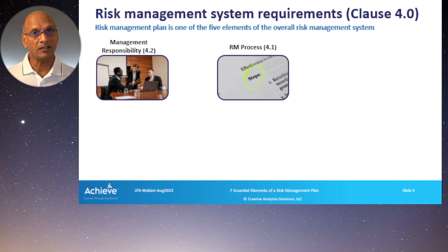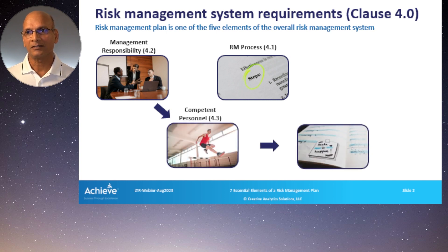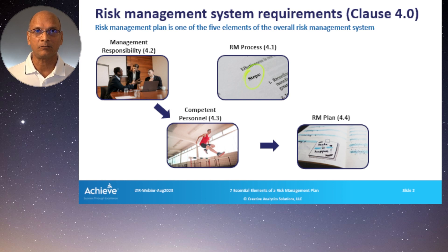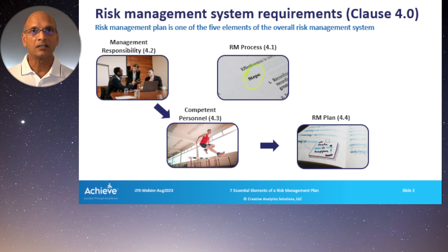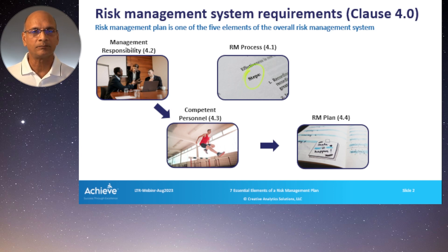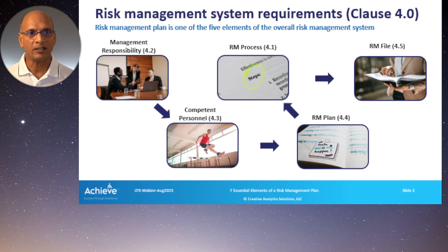Before the process can start, we need management responsibility to be clearly defined — that's in clause 4.2. They will assign competent personnel who would set up the risk management plan. All those pieces have to be in place first. The risk management plan is very focused and targeted for the particular product you are working with, or a family of products — it doesn't have to be only one product. It can be a family of products if they are sufficiently similar in their intended use and technological characteristics. Once you execute your process, the output of that process is the risk management file.